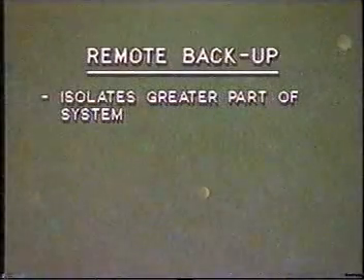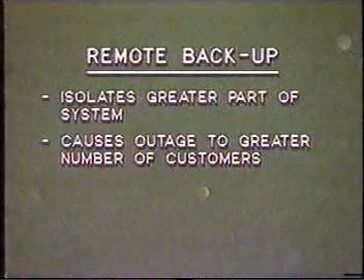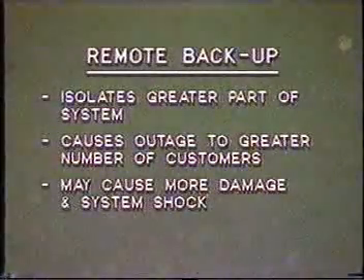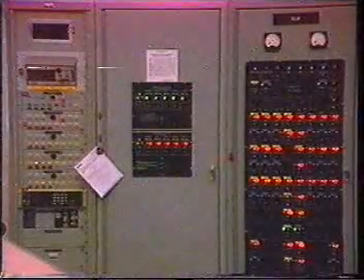Remember, remote backup will isolate a greater part of the system and perhaps cause outage to a greater number of customers. Also, there may be more damage and system shock. In this context, inter-tripping using various communication channels could be used. We'll discuss this in future tapes.